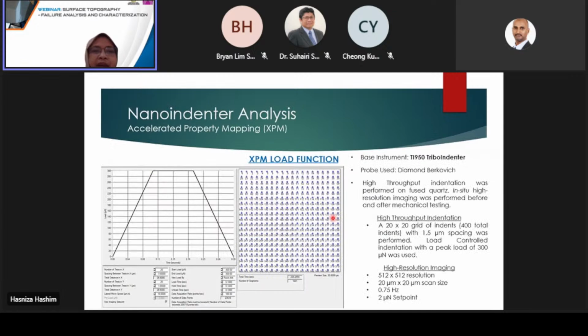Last but not least, this is the accelerated property mapping. When we want to do the XPM testing, we need to use only trapezoid load functions, and then we need to set how many indentations we want to do. For example, for this one, I want to do 20 by 20 with the spacing between each indent being 1.5 microns. So a total of 400 indentations will be performed, with the maximum force that we apply up to 300 micronewton.